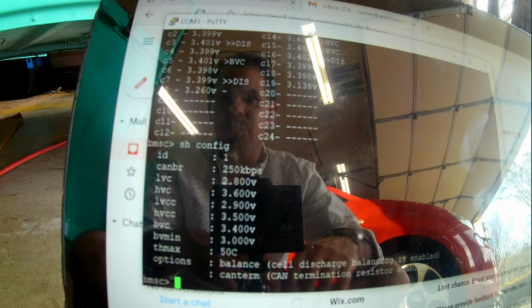Second to last, thermistor max, or TH max, is set to 50 degrees C. If the temperature rises above 50 C, the charging will stop and an alert will sound. Finally, the following options are enabled: one, balance cells on discharge, and two, the built-in CAN bus termination resistor is active.